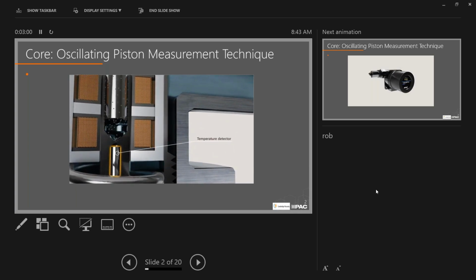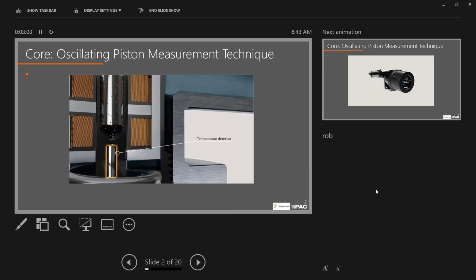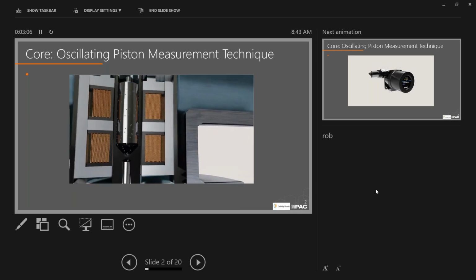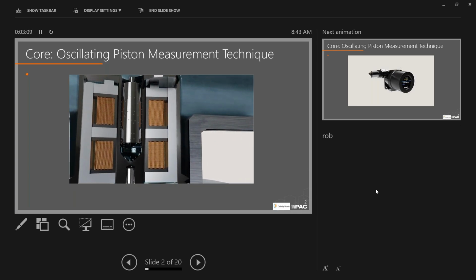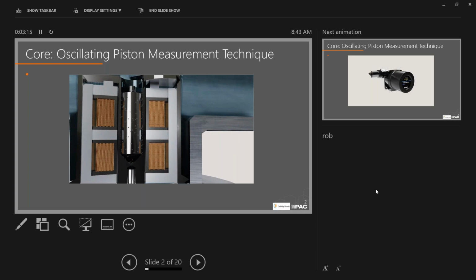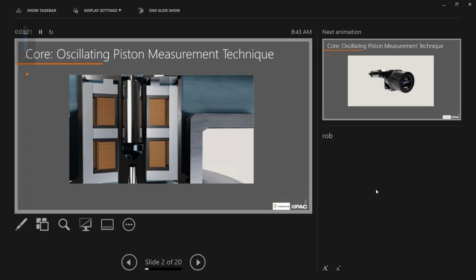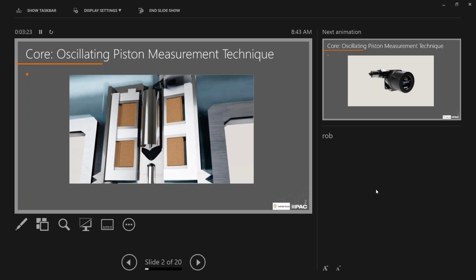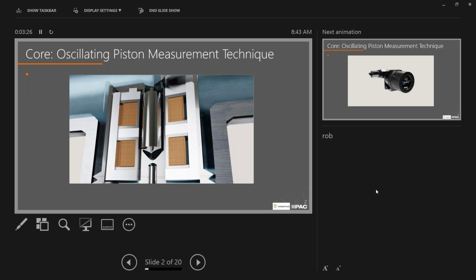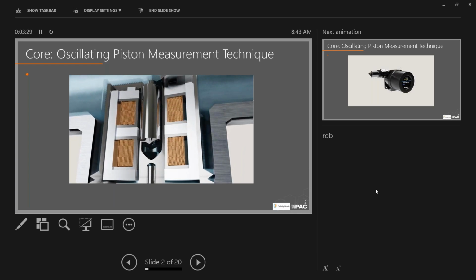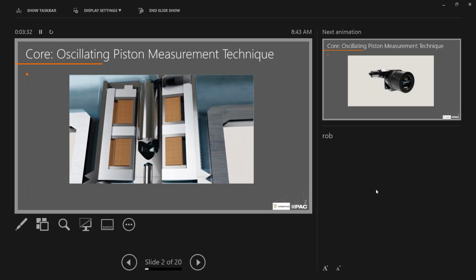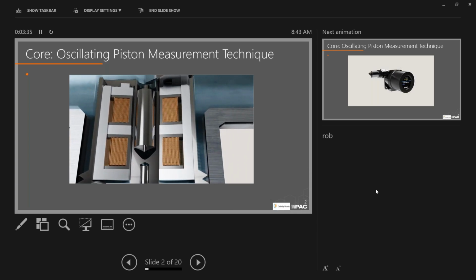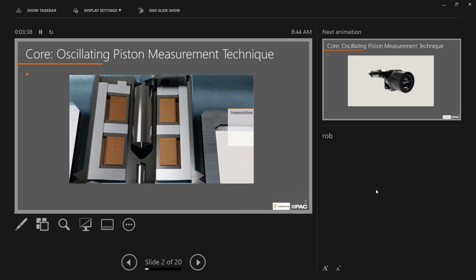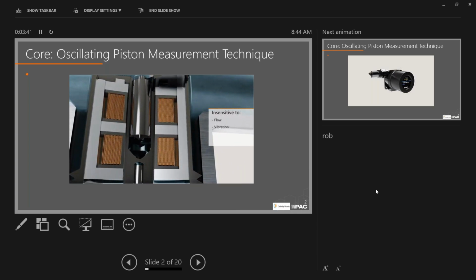An internal temperature detector senses actual temperature inside the measurement chamber. The system can calculate temperature compensated viscosity, which increases its accuracy under the ever-changing environmental conditions for direct comparison with laboratory data. The electronics can also provide the current shear rate at the measured viscosity. Since all the parts that can become wet are made of stainless steel and the piston is in constant motion, the sampling area is continually scrubbed clean to prevent fouling. The system holds its calibration and requires little to no maintenance. It is insensitive to flow, vibration, particles, or entrained gas.